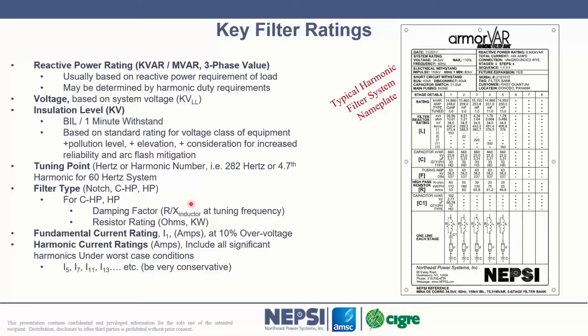So, reactive power. When you look at key filter ratings, the first key filter rating is reactive power, and it's usually based on the requirements of the load. So a load study gets done, somebody develops a spreadsheet, or somebody does a harmonic load flow study. They come up with the 60 hertz or 50 hertz reactive power requirements of the facility, and that's usually the first parameter that defines a harmonic filter. The first parameter that defines a harmonic filter is its reactive power output rating.